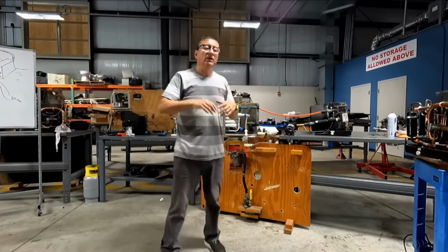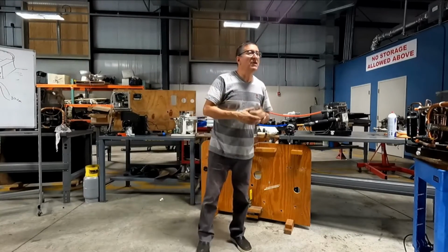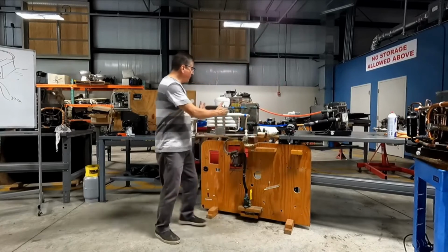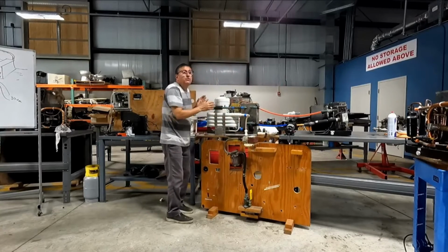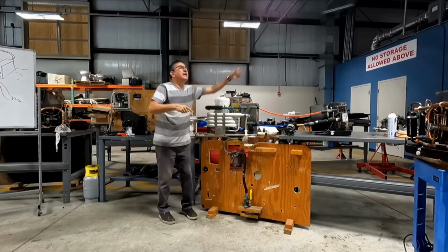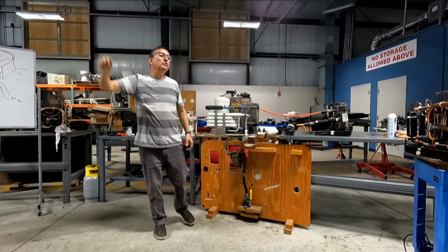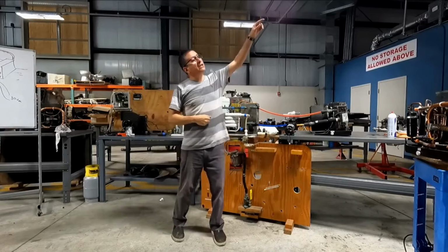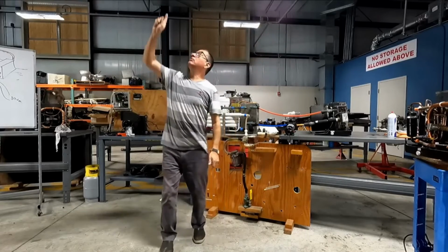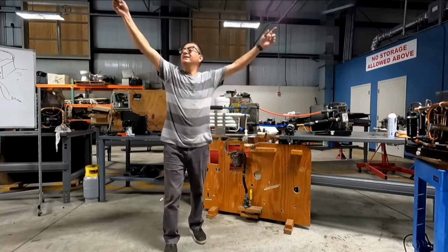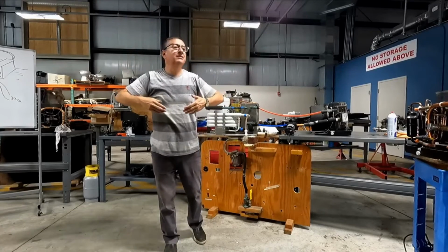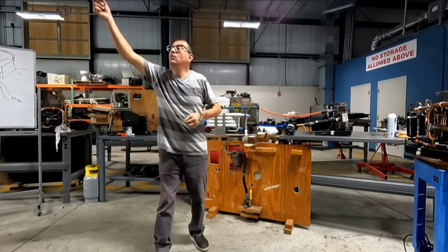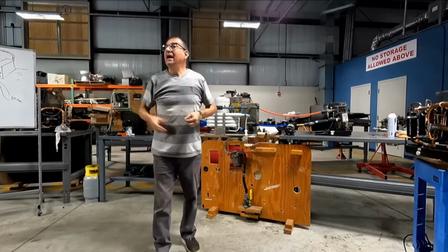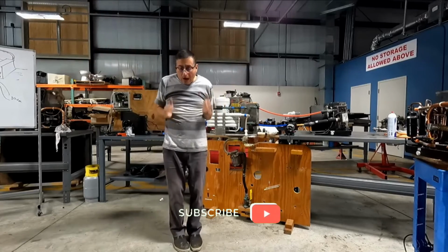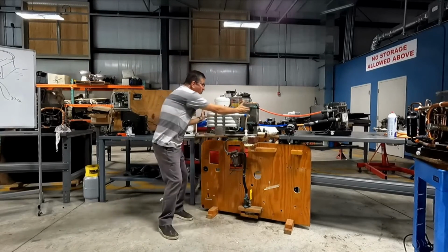Now, every day it is more popular in big boats, because you only have one small unit with refrigerant here, and the rest, in between the master room and the central unit, in between the galley and the central unit, in between the flybridge and the central unit, is not a split unit. It's pipes with the coolant or fresh water, and air handlers. You only have one air conditioning unit here in the center.